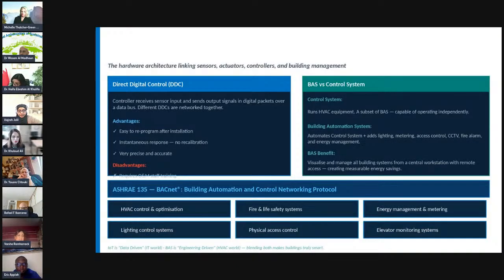Hardware architecture links sensors, actuators, controllers, and building management—direct digital control, your BAS versus your control system. BAS is the building automation system. The controller in the DDC receives sensor inputs and sends output signals in digital packets over the data bus, and different DDCs are networked together. The advantages are easy reprogramming after installation, instantaneous responses with no recalibration required, and very precise and accurate control.